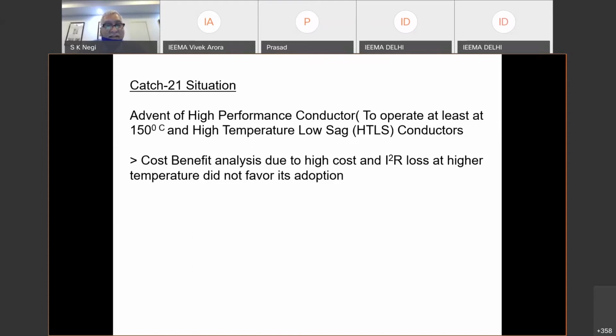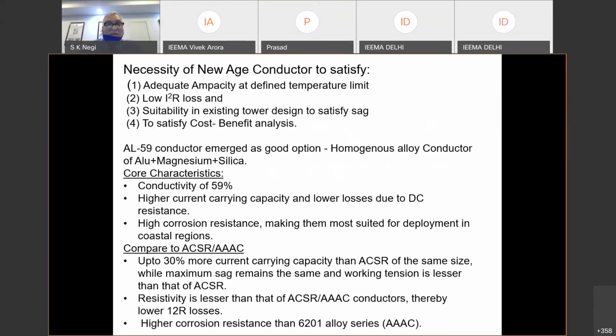So this name itself, new age conductor, was given by the designer of this program. I'm very happy that it is being discussed, and now we'll go further into how this conductor can be used in the present arena of transmission lines, particularly when RE is increasing day by day. So with this background, for the necessity of a new age conductor, four factors I feel were important, which we considered: adequate ampacity at the defined temperature limit, low I square R losses, suitability in the existing tower design to satisfy sag.